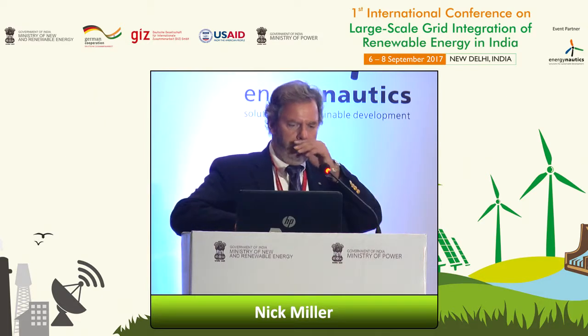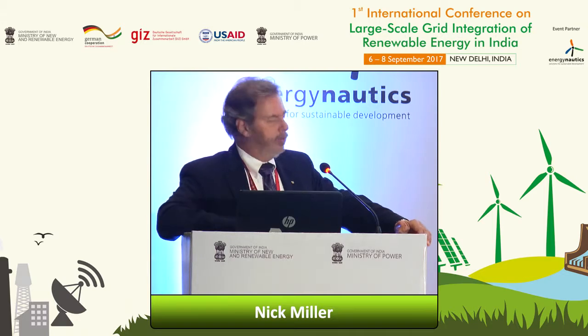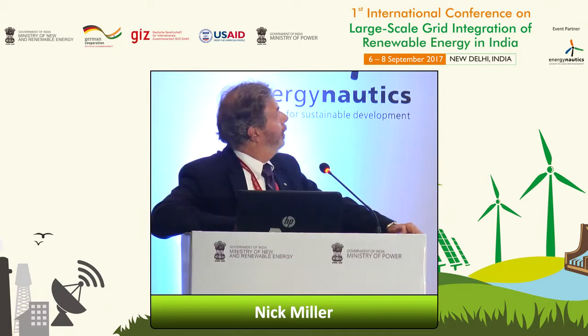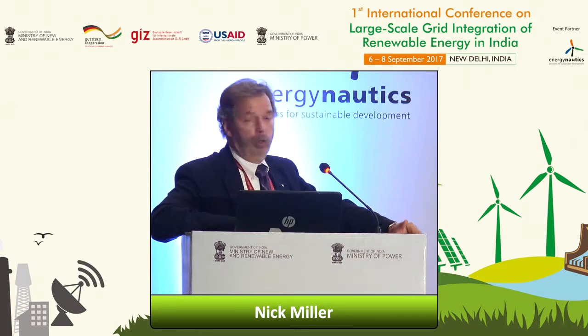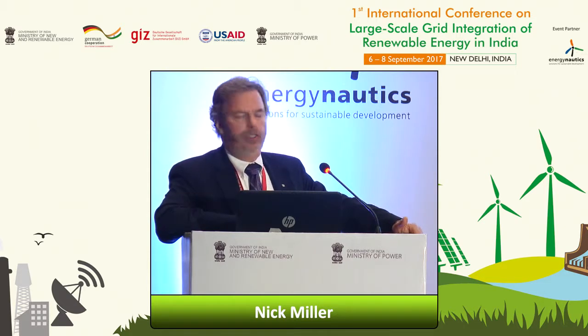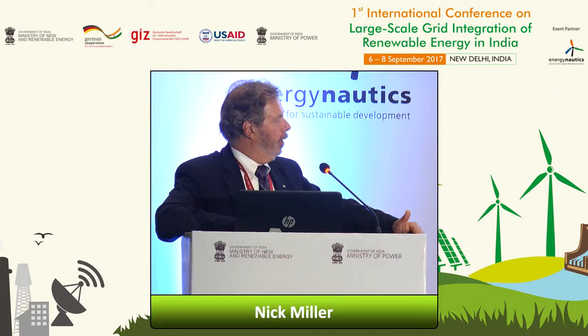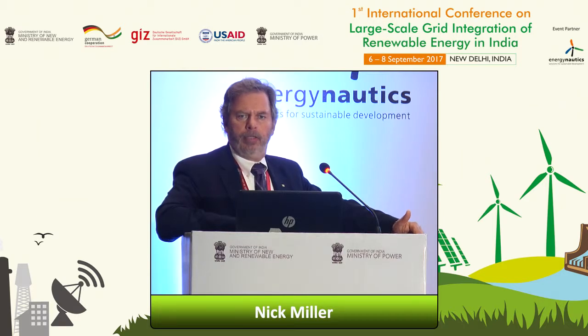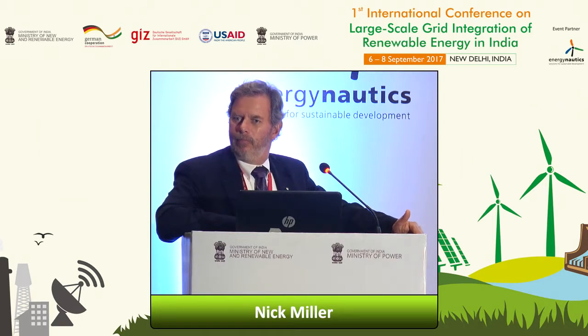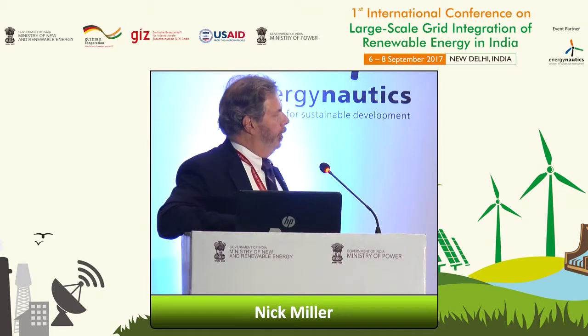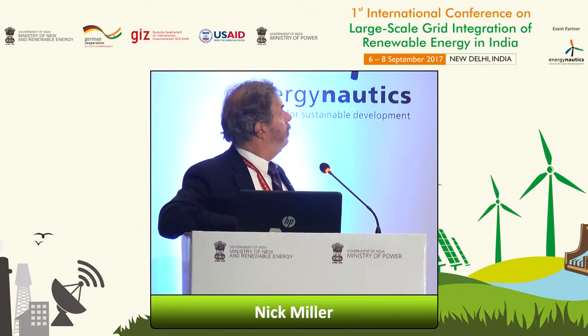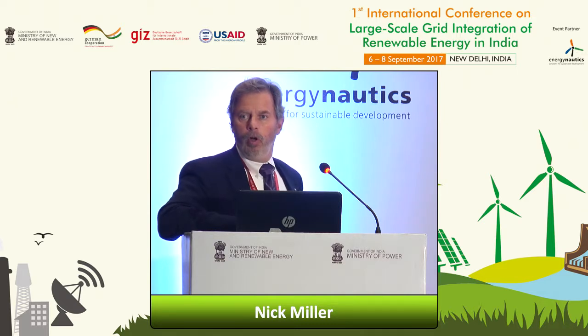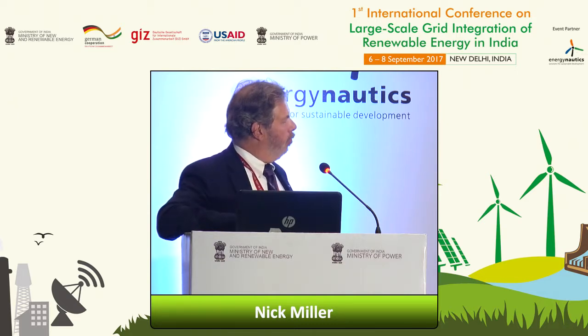So I'm going to give you a little context, and this is a field test. It's not particularly important, other than that this is a typical commissioning test for a wind plant, where it comes with factory set settings, and then part of the commissioning exercise is to give steps in voltage reference and make sure you get nice, stable, well-mannered response with no overshoot.